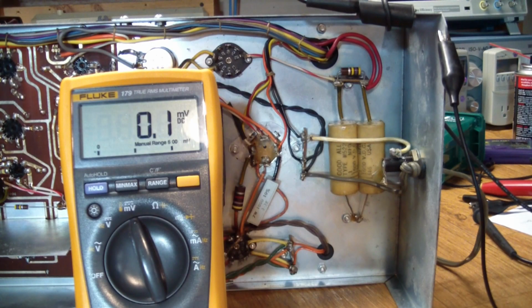So what I'm going to do, or show on camera, is I measured some high voltages. They were a bit low, probably 5 to 8% low, but the schematic does say, and let me quote, "voltage variation up to 20% normal." Now, what I'm assuming is it's talking about plus or minus 10% from the listed value, and not 20% in either direction. So generally, we are within that.